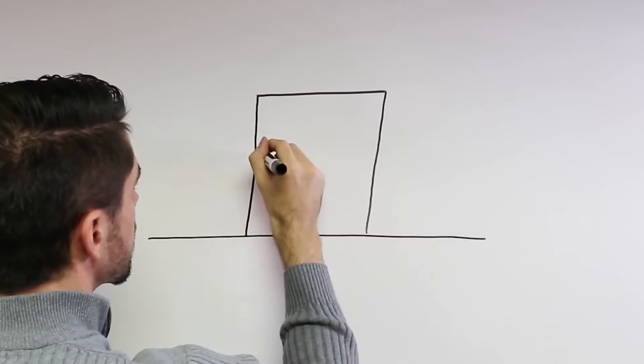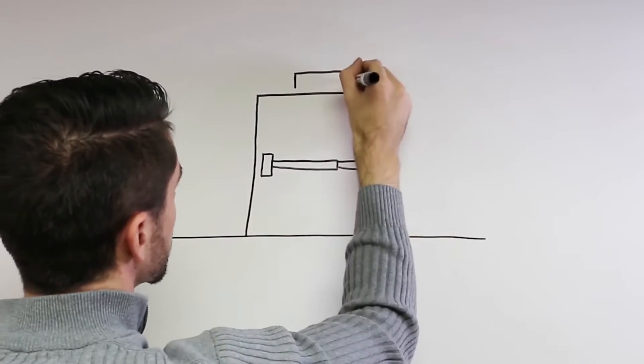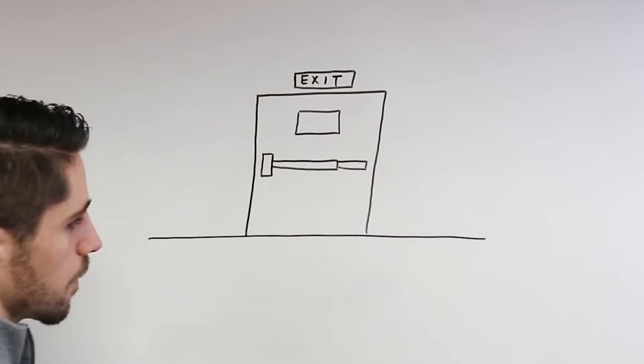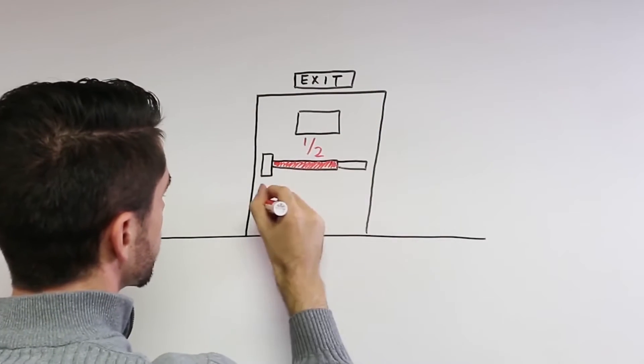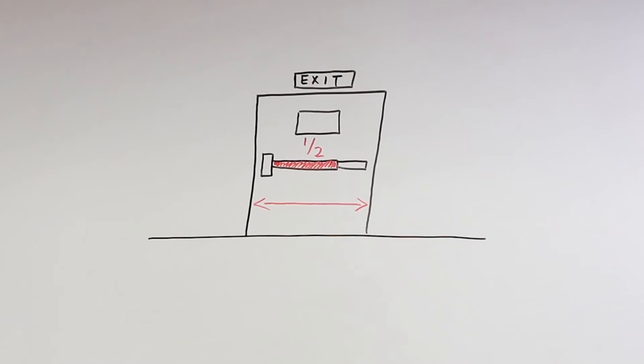When codes require exit hardware, the actuating portion of the device must be at least half the width of the door leaf. That's so when a person or persons are exiting in a hurry, it is easy for them to find the device.